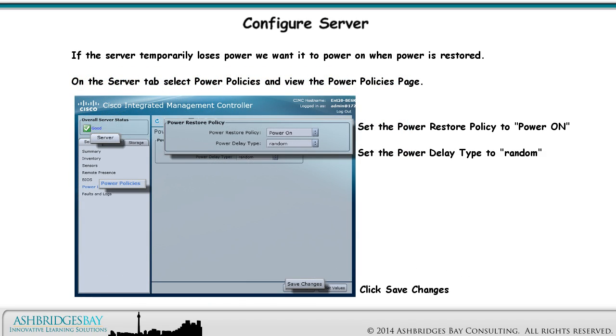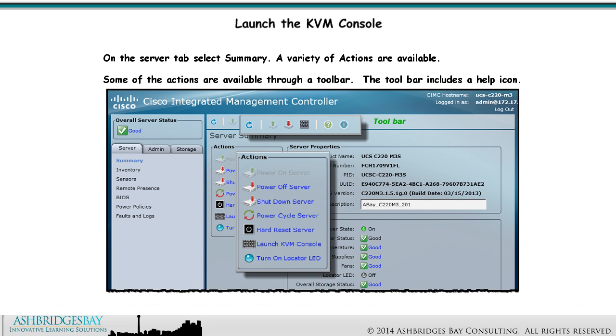If the server temporarily loses power, we want it to power on when power is restored. On the Server tab, select Power Policies and view the Power Policies page. Set the Power Restore Policy to Power On and set the Power Delay Type to Random. On the Server tab, select Summary. A variety of actions are available: Power On Server, Power Off Server, Power Cycle Server, Hard Reset Server, Launch KVM Console, and Turn On Locator LED. Some of the actions are available through a toolbar, which includes a Help icon.